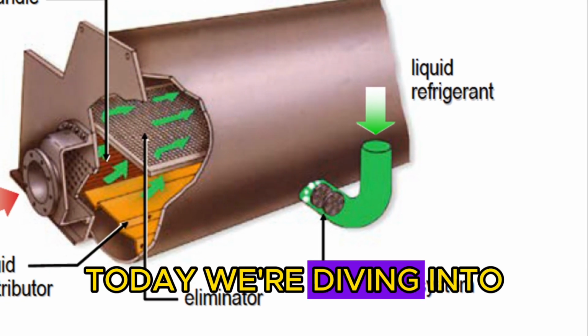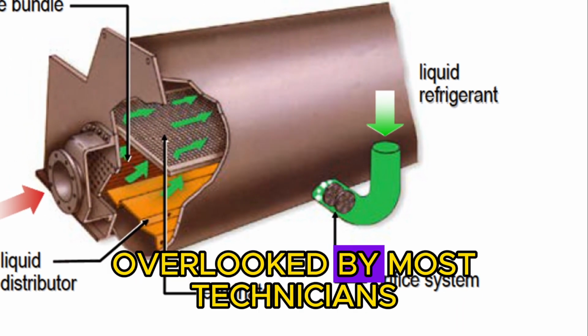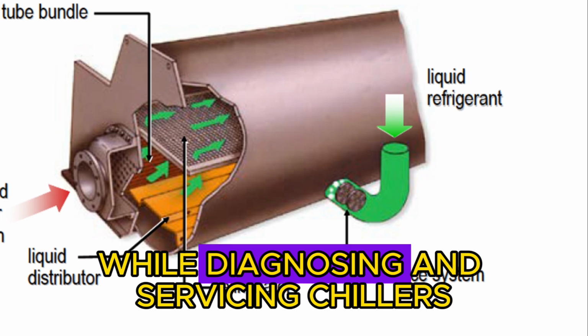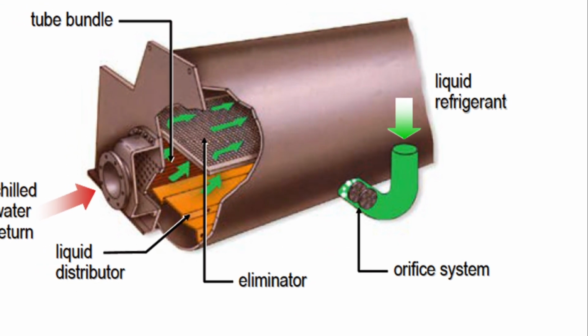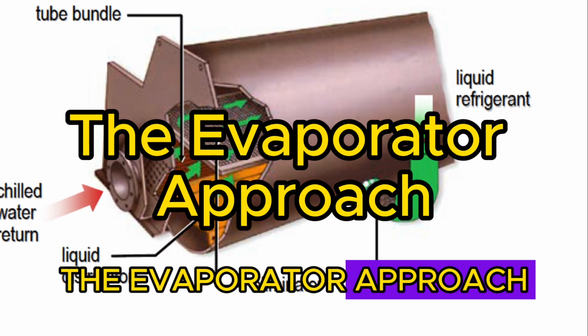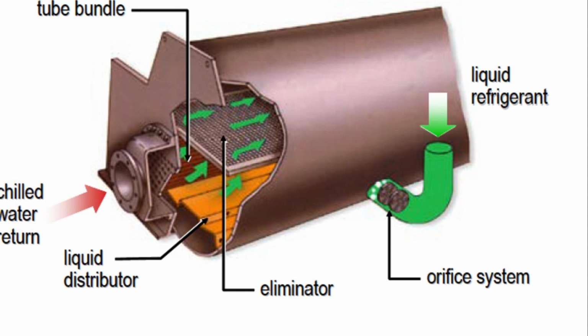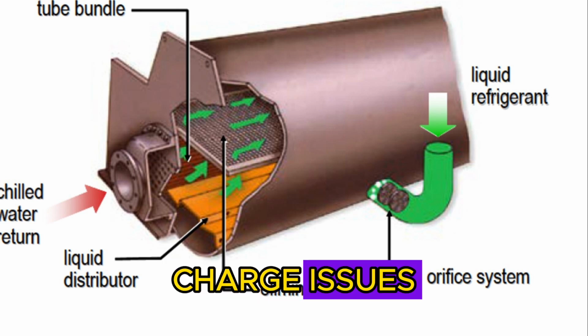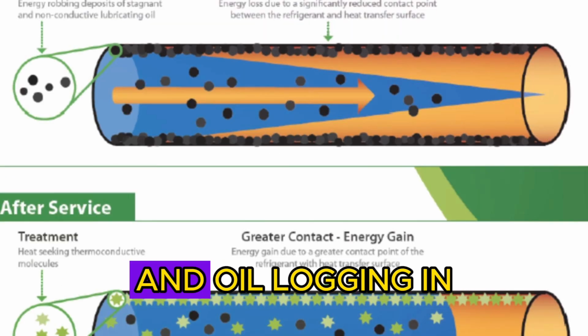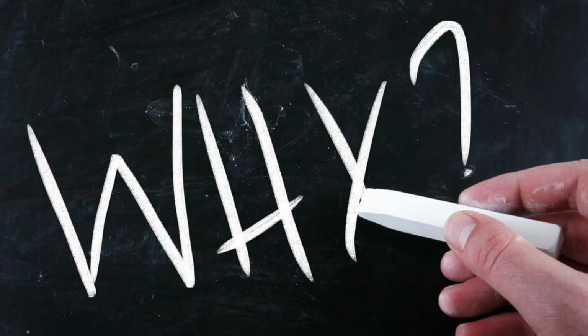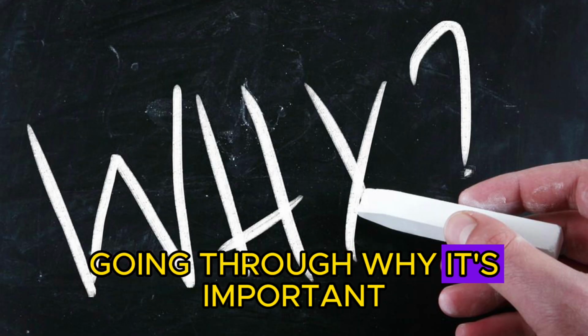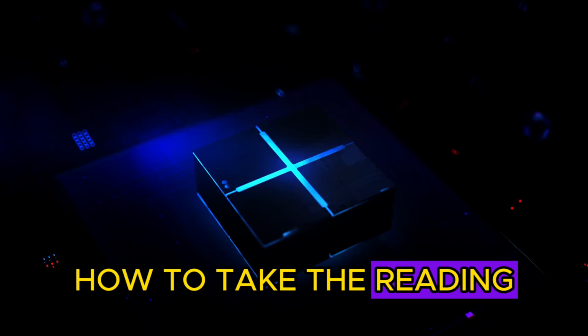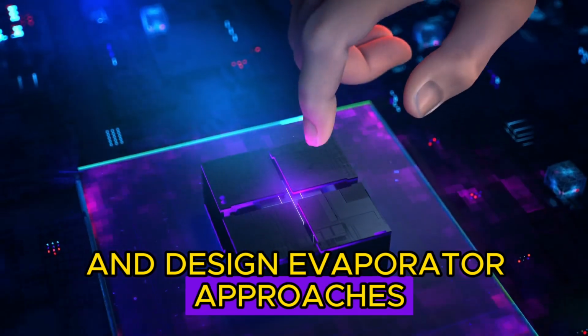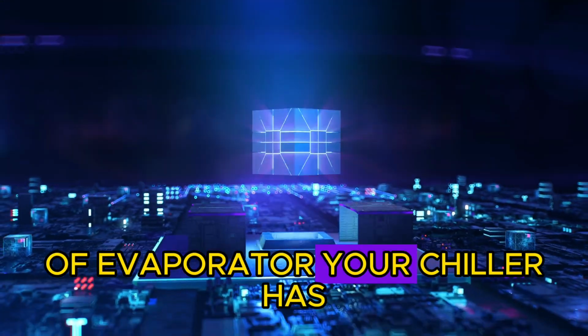Today, we're diving into a reading that tends to be overlooked by most technicians while diagnosing and servicing chillers. The evaporator approach. Using this reading will help you diagnose refrigerant charge issues, dirty evaporators, and oil logging in the evaporator. We're going to be going through why it's important, how to take the reading, and design evaporator approaches based on the type of evaporator your chiller has.